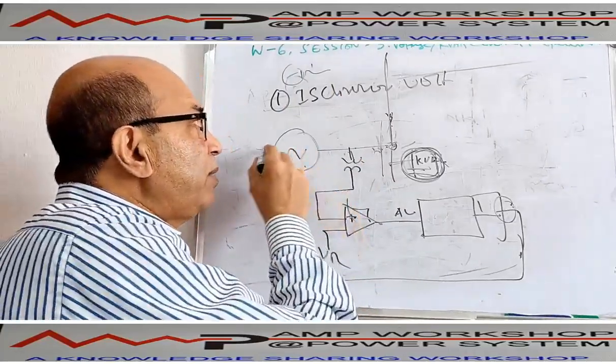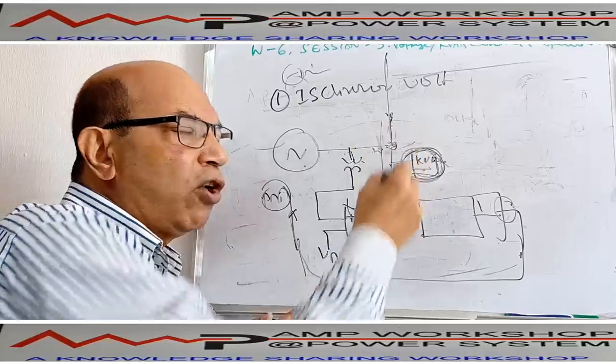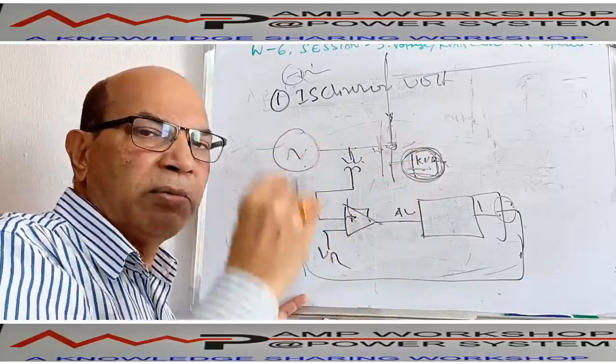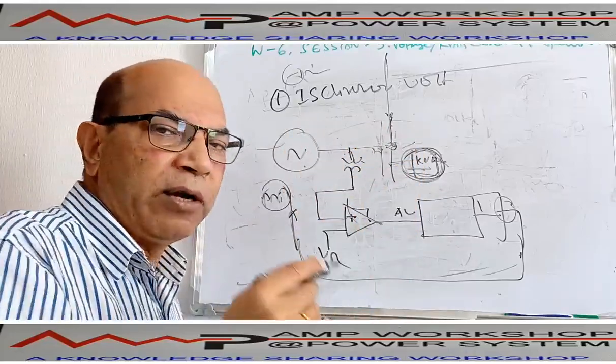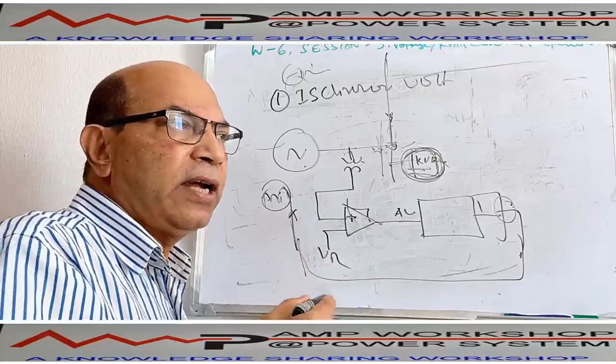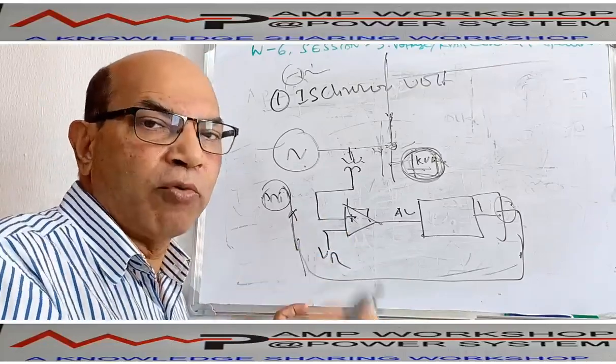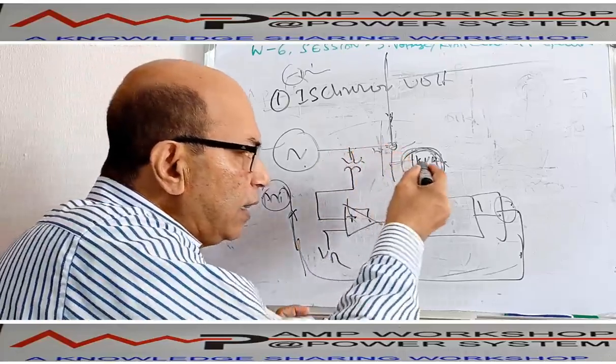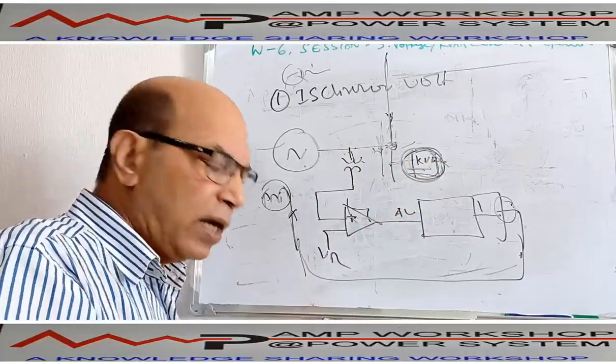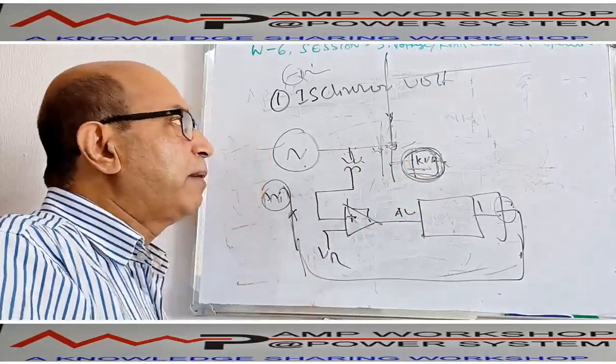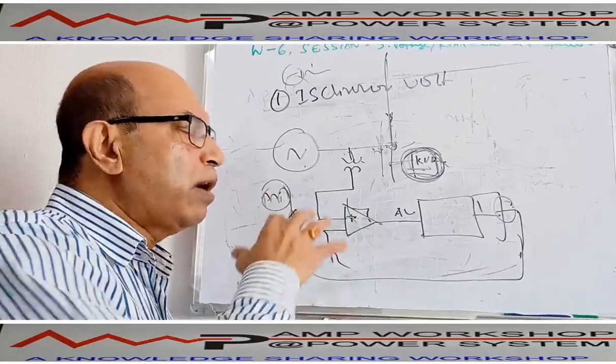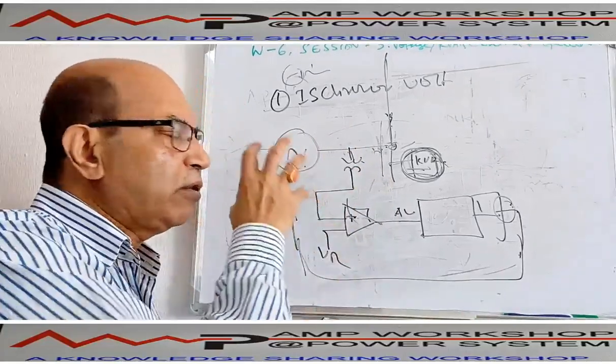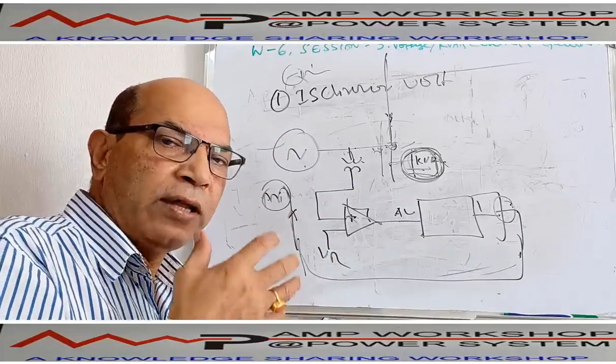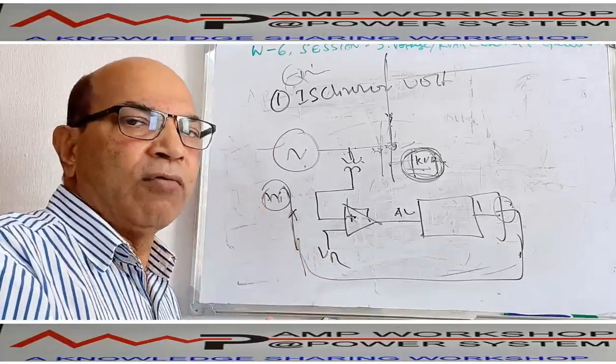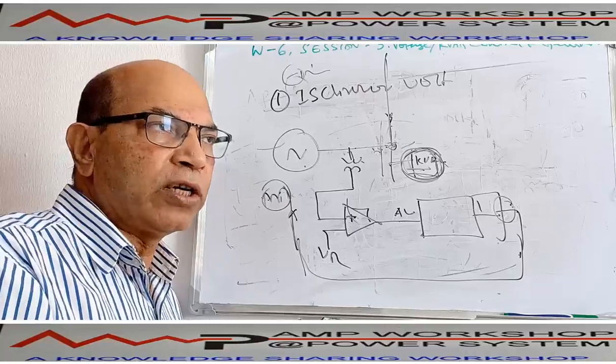So there is a chance of instability amongst the machines. The voltage will not be stable. The voltage will be fluctuating. It will be dancing because the machines are not able to cope, or cannot decide who will take what amount of KVAR. That's the reason that when multiple machines are there, it is not preferable to run the machines in isochronous voltage mode. We have to go for the other mode. So we operate in isochronous voltage mode only when a single machine is running. We can use isochronous voltage mode then.